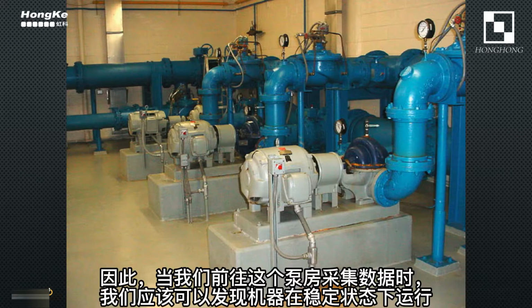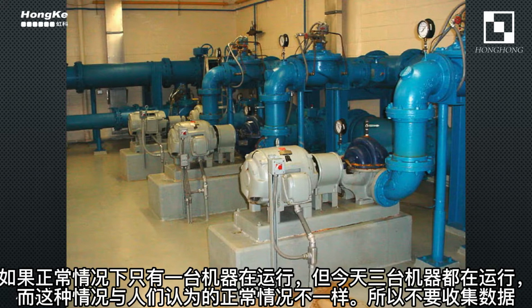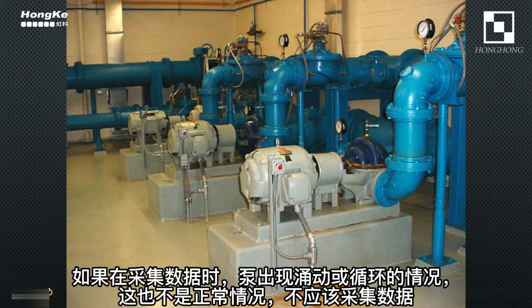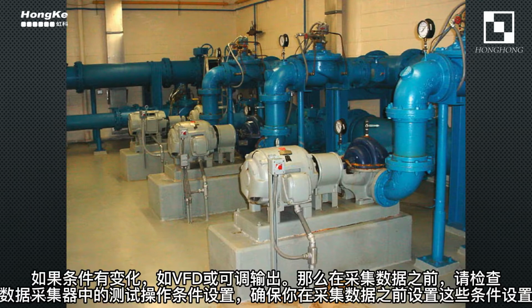So as we head to this pump room to collect data, we should find the machines running in a steady state condition. If normally only one machine is running, but today all three are running, well, that condition's not the same as what is considered normal, so don't collect data. If while collecting data the pump surges or cycles, again, this isn't normal condition and you should not collect the data. If there are variations to the conditions, like a VFD or an adjustable output, then review the test operating conditions in the collector application before collecting the data. Make sure you set those before you collect the data.